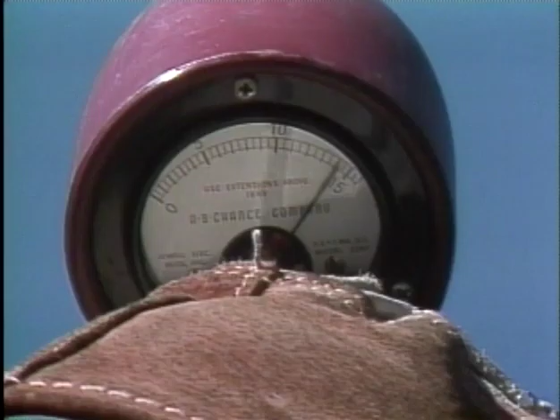You've seen how noisy testers, stethoscopes, and phasing test sets confirm whether or not a circuit is de-energized. We also looked at some of the steps you need to take to ensure your tester gives you accurate results. In the examples we showed you, the circuits we tested proved to be dead. However, that won't always be the case when you're testing out in the field.